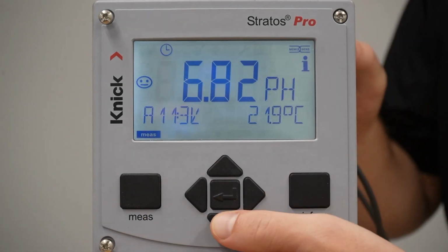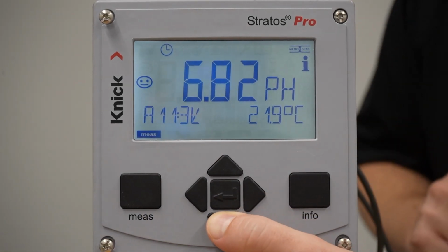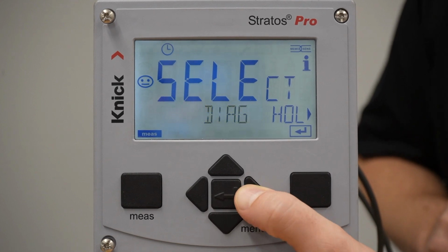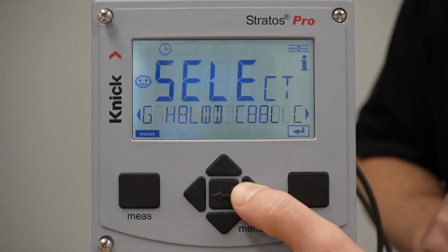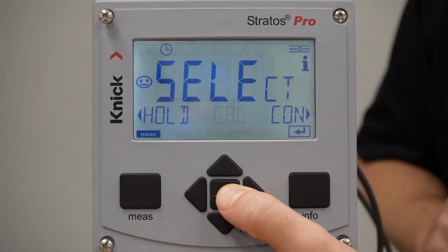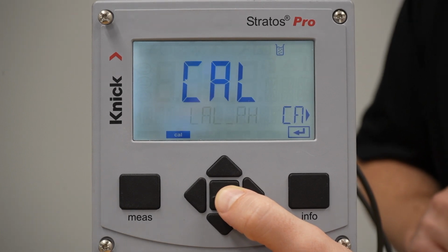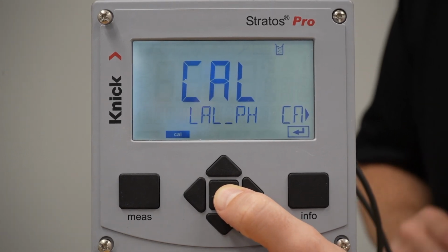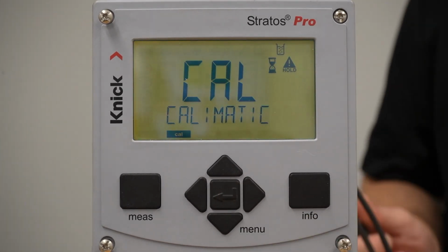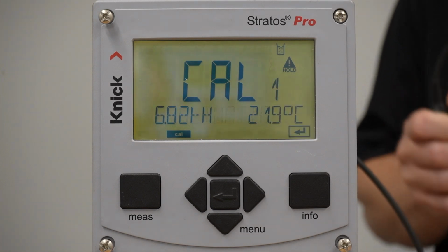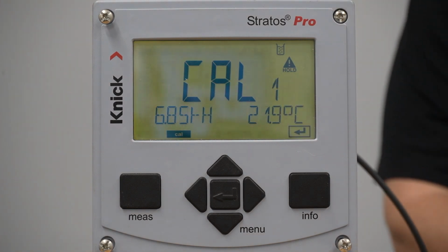To begin, we will hit the down button to go to the menu. We will then scroll over to the calibration menu. Once here, we will select Cal pH. We will have it set in Calimatic, which will automatically identify the buffers we will use.